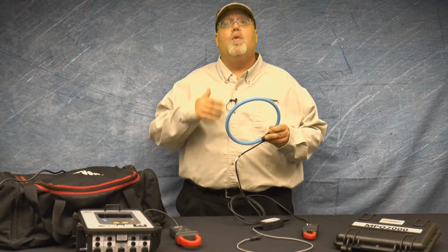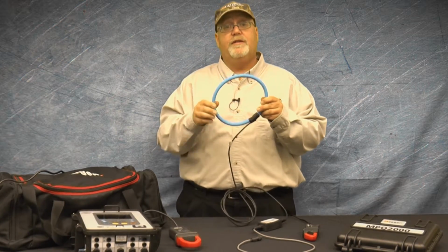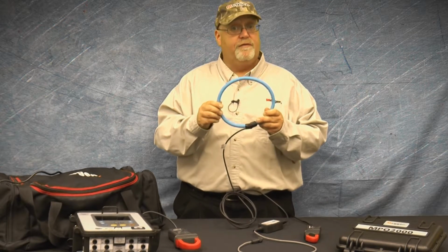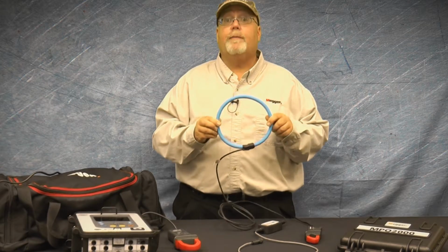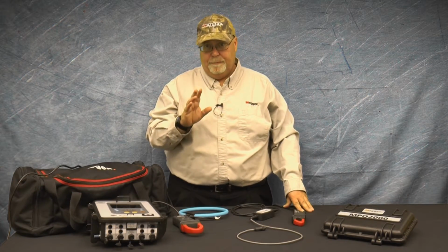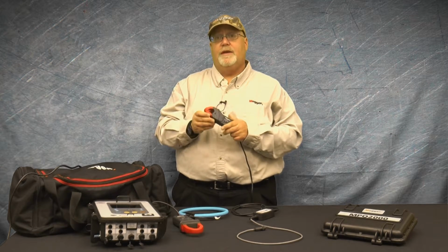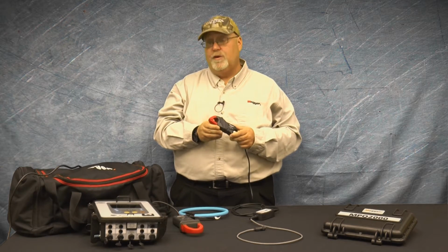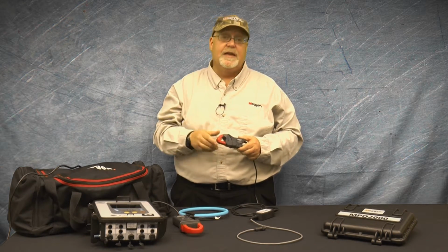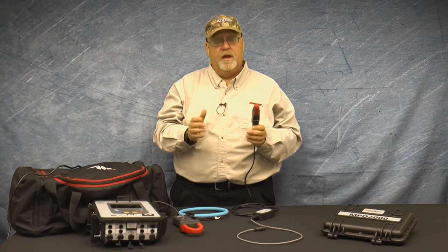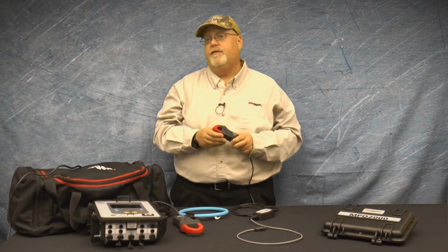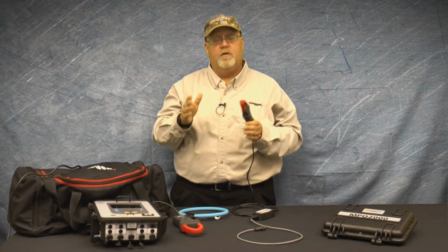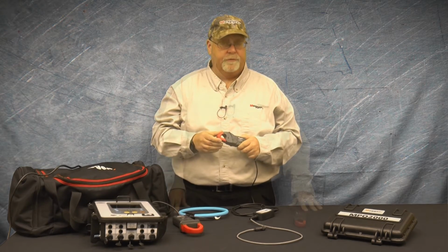Step 5. What is the voltage on the line you're going to be putting the CT around? You want to make sure that the CT is rated for that voltage level and the insulation provides proper protection. Another thing to keep in mind is if you're taking a measurement in a substation on the secondary of a substation CT, take note of the bandwidth of that substation CT. Typically, these have limited bandwidths, which means they can cause inaccuracies if you're attempting to do a harmonic analysis. So this is something to keep in mind if you want to do harmonic studies in substation environments.